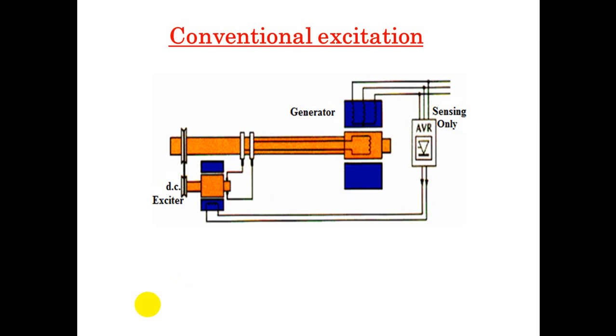What are the commonly used generator excitation systems? There are six commonly used in a generator excitation. 1. Conventional excitation, as shown in this picture. What happens in this excitation? A typical schematic of a conventional method where a driving DC exciter, in this case belt driving, feeds its DC output through slip rings to the main generators.